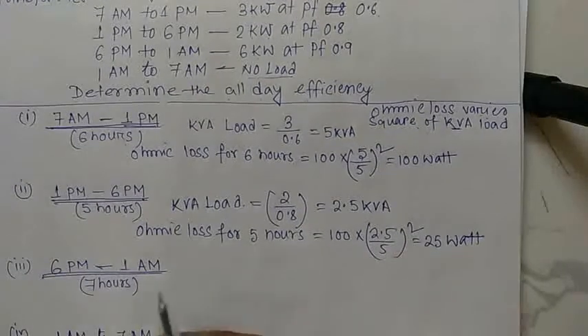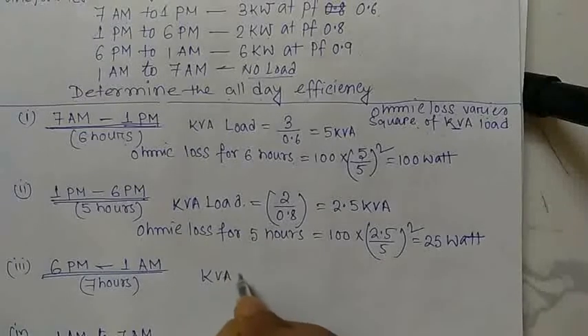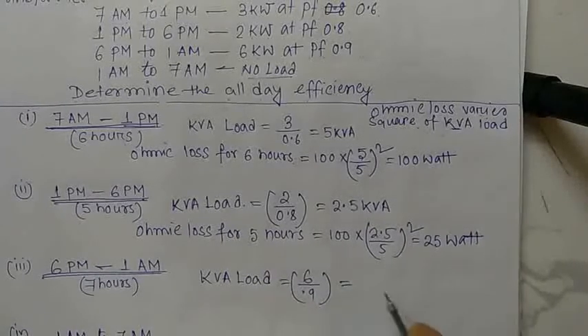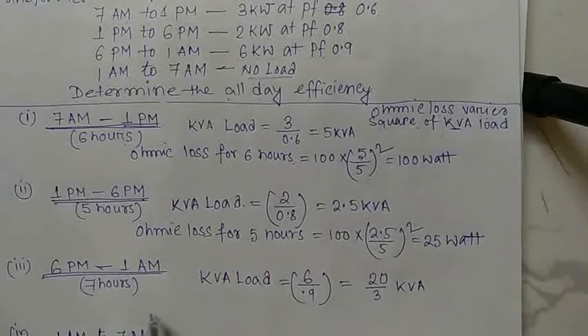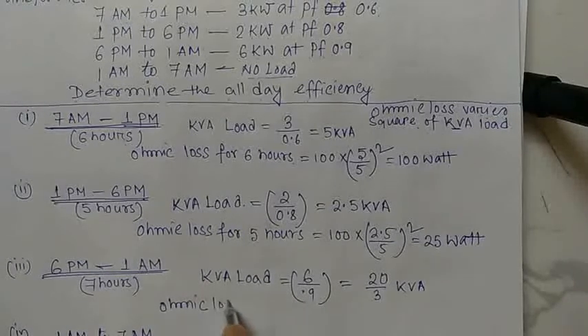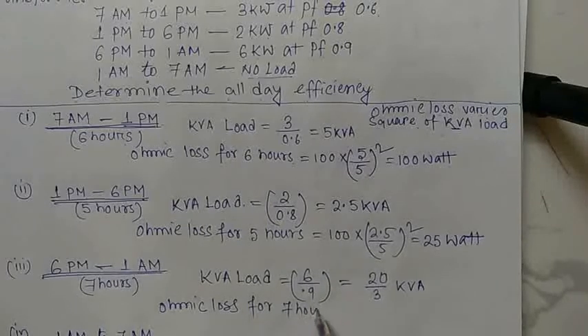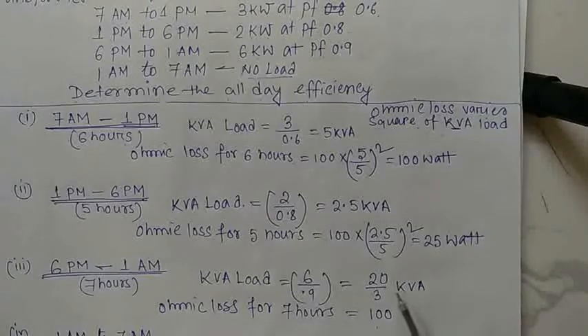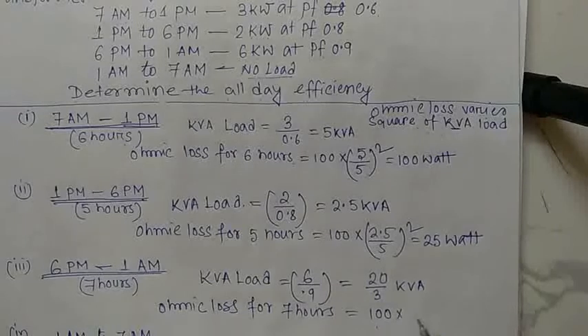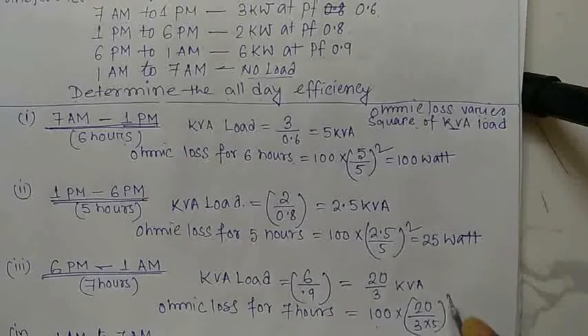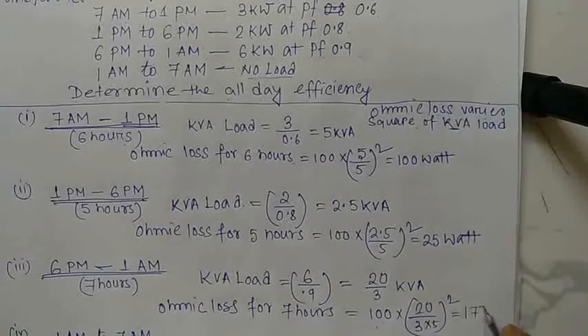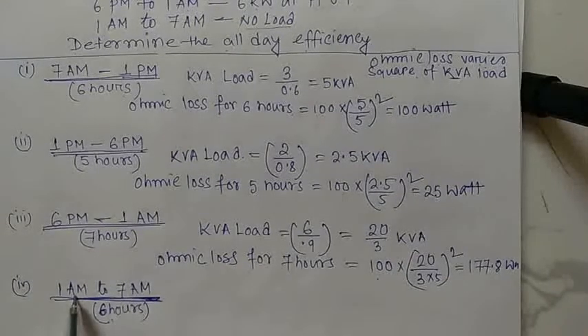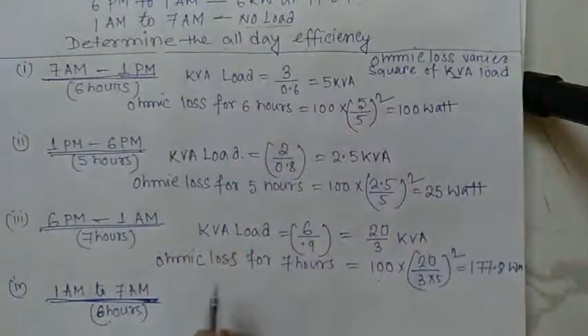For 6pm to 1am (7 hours), the kVA load is 6 kW divided by 0.9 = 20/3 kVA. The ohmic loss for these 7 hours is 100 × (20/3 ÷ 5)² = 177.8 watts.